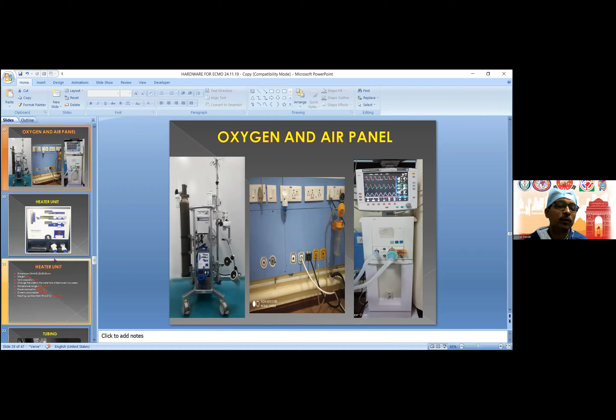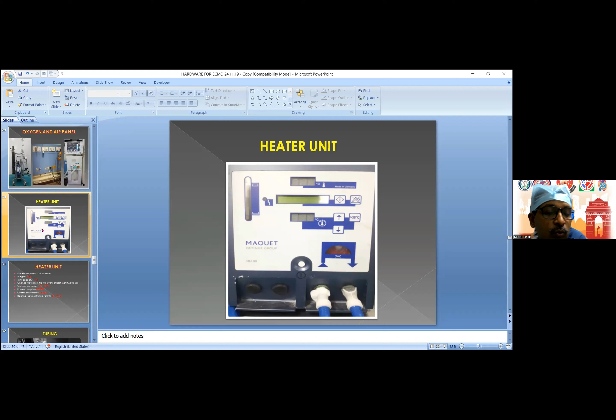Heater unit. Most of the blood is passed through this extracorporeal circuit, and the ICU temperature is 20 to 30 degrees, which most ICUs maintain at less than body temperature. If blood passes through at a temperature lower than the body throughout the day and for more than a day, the circuits pass heat out through the circuit. So we have to maintain the temperature of the patient. As the clinician instructs, it should be 35 to 37 degrees, so we have to introduce a heater in the circuit.